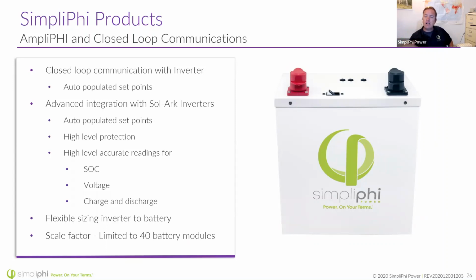Another thing to note is that the SimpliPhi batteries have a slightly higher max discharge rate at 100 amps for 10 minutes. This is a 100 amp built-in breaker here, whereas the standard Phi batteries have an 80 amp breaker, so they can do 80 amps at 10 minutes.